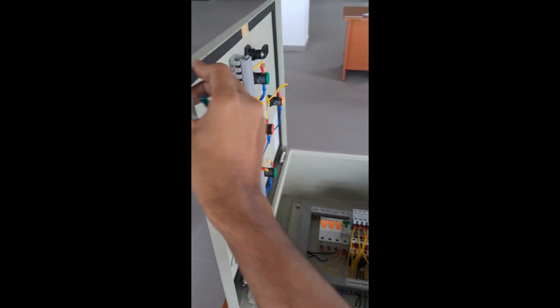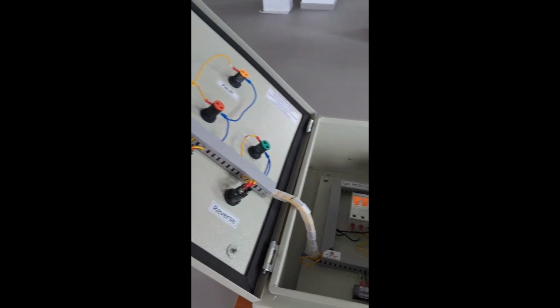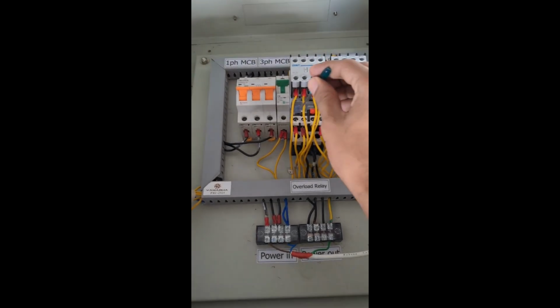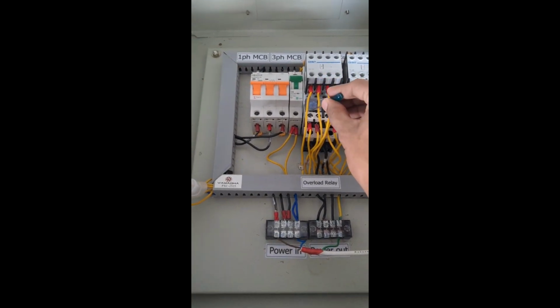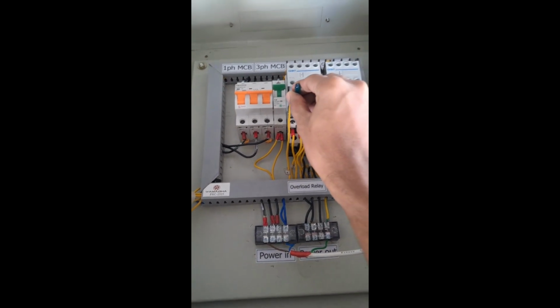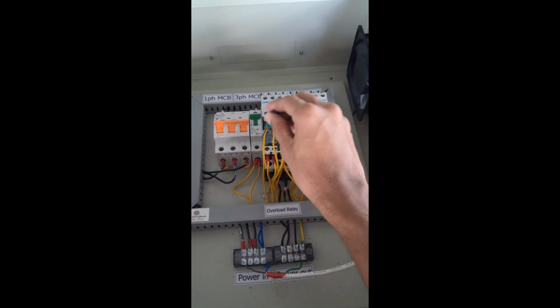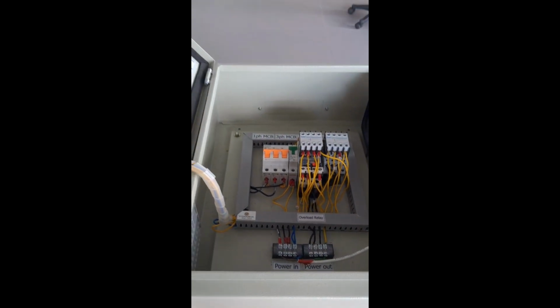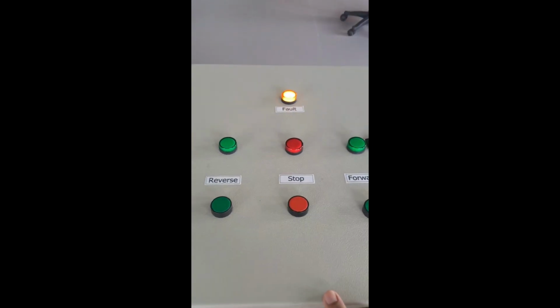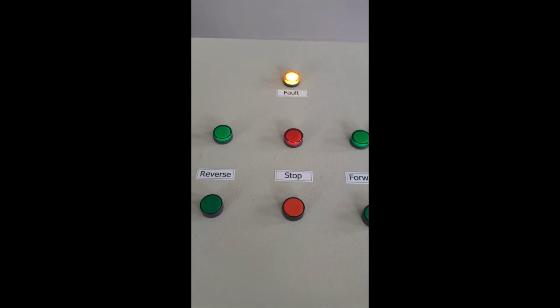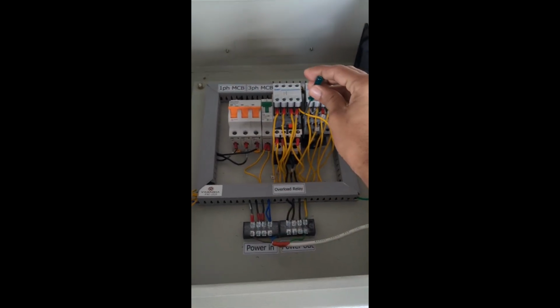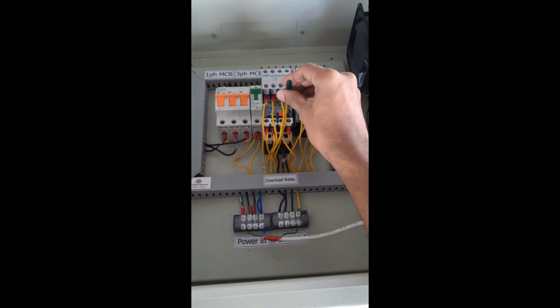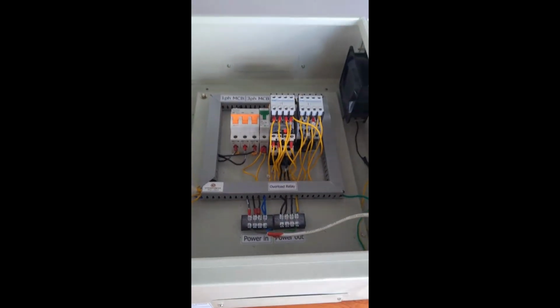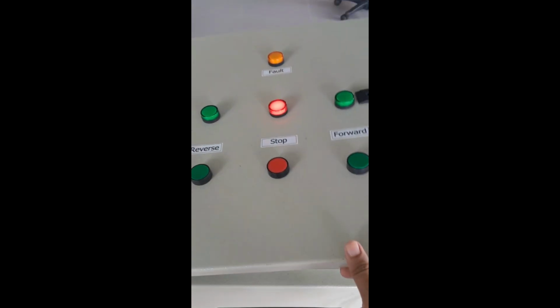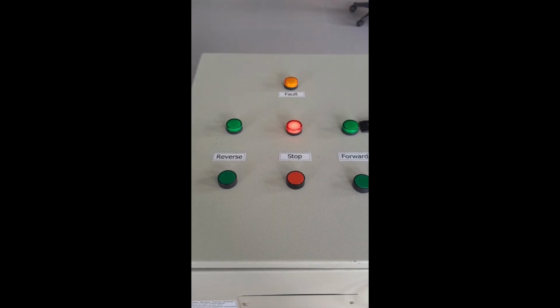So we can see the fault by manual triggering of the overload. So there's an overload trigger. We have to press it, so that will enable the overload relay, and the fault light will light up. Then we have to reset the system or reset the overload relay. Only then can you go back to the initial state or the stop position of the motor.